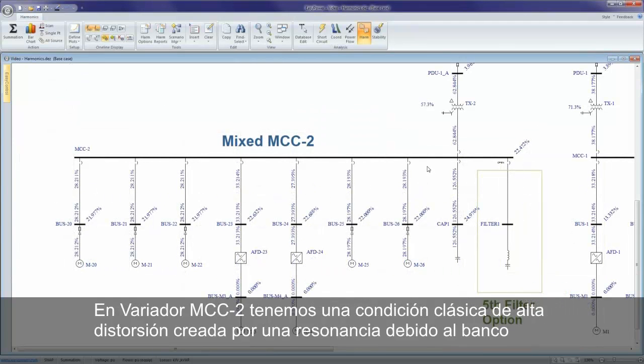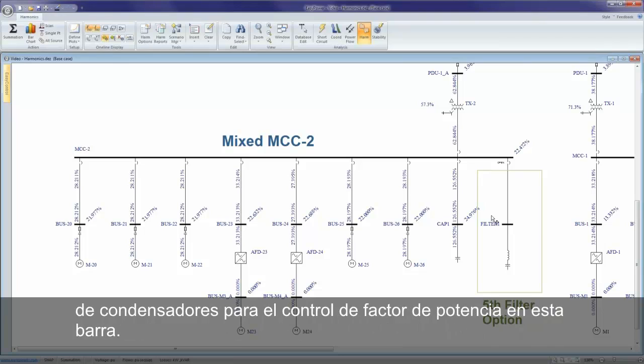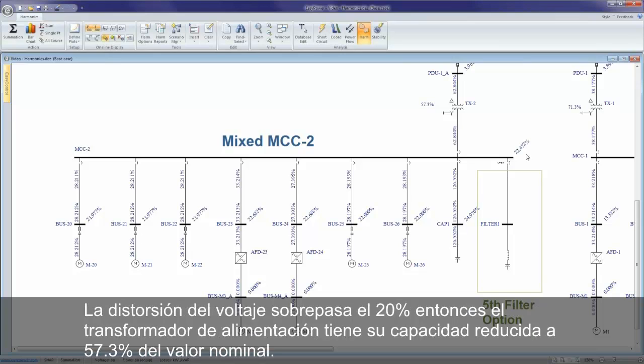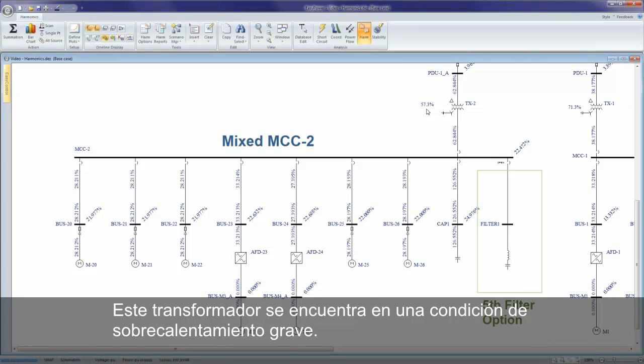At MCC2, we have a classic high distortion condition, which is created by a resonance due to a power factor correction capacitor connected on the bus. Voltage distortion is exceeding 20% and the supply transformer is derated to 57.3% of its capacity. This transformer is in a severe overheating condition.